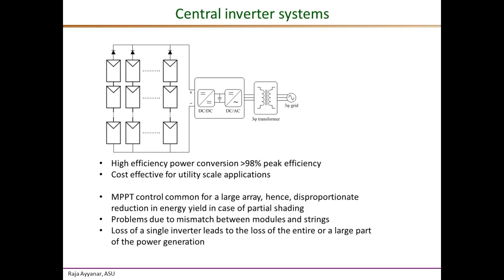Central inverters tend to have the highest efficiency among all inverter types, with recent products exceeding 98% peak efficiency. They are also the most cost-effective solution for utility-scale applications due to fewer inverters needed. However, drawbacks include a single MPPT for a large array, so partial shading or module mismatch causes disproportionate energy losses. Additionally, loss of a single inverter can take down a very large section of the power plant.